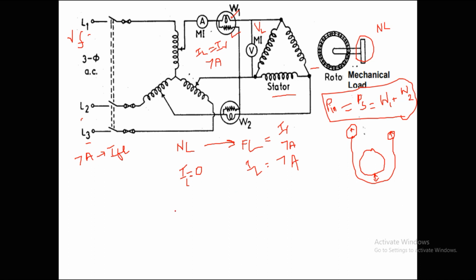But practically it's not possible, especially at no load condition, because even at no load there will be a flow of current, since we get flux creation in the machine and we have to compensate for the constant losses. So for that there will be a flow of current even though we are not having any load in the induction motor. So we can expect 20 to 30% of the rated current at starting.